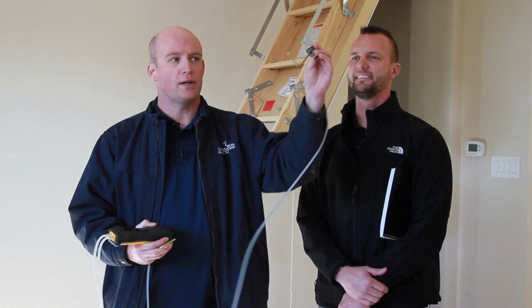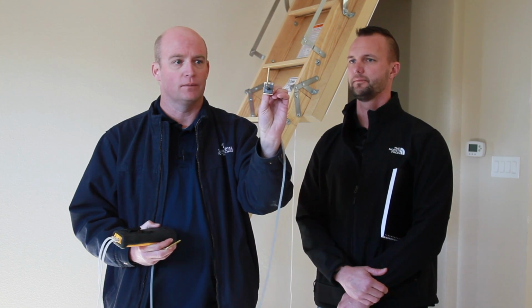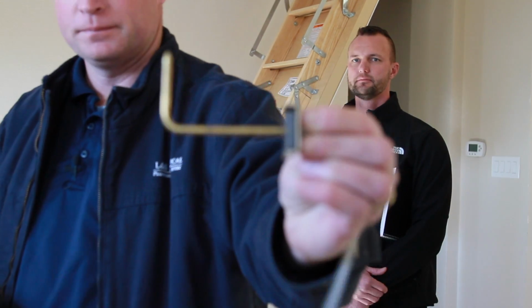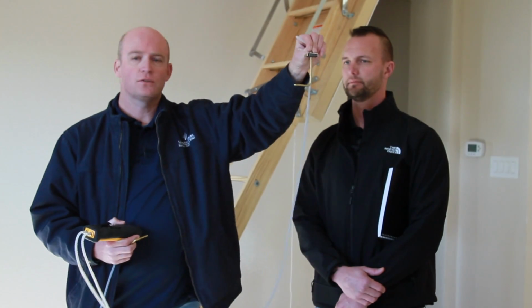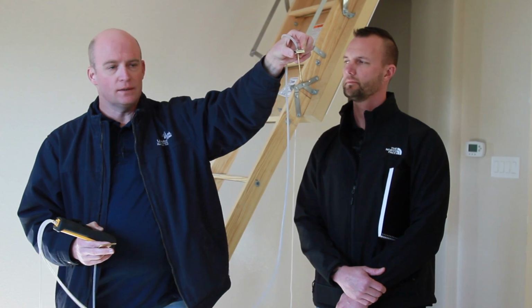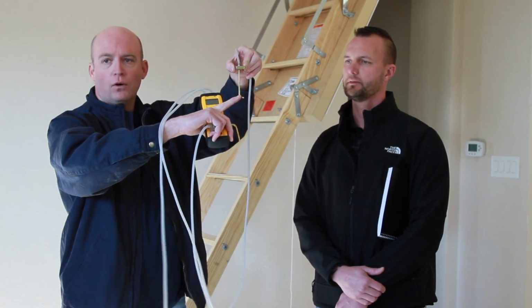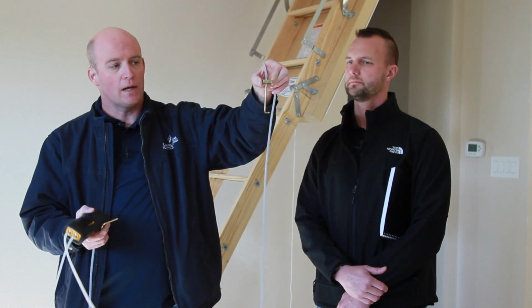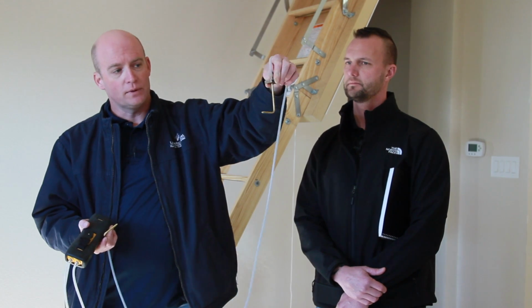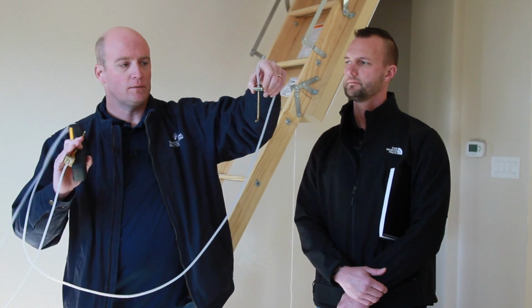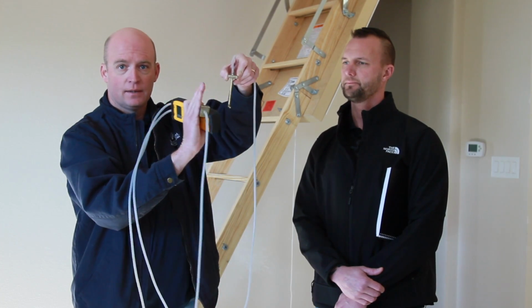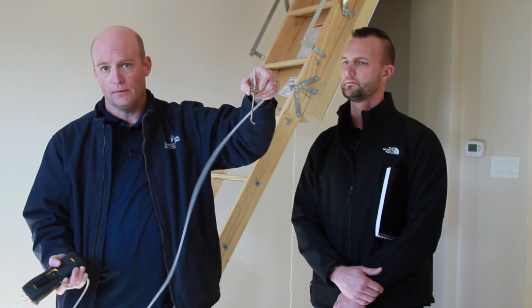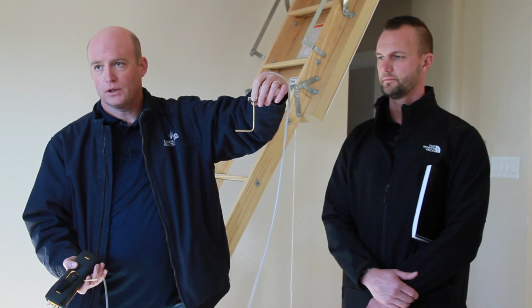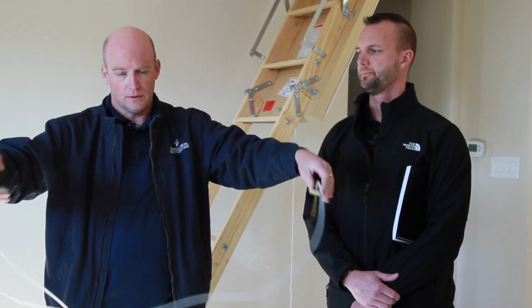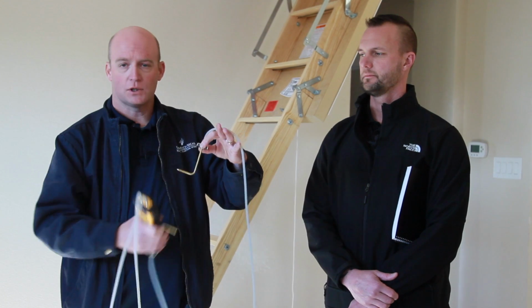If you'll notice, the probes have a point. It's not a pitot tube, but it's similar. And on the sides, there are holes. We want the probe to be pointing in the direction of the airflow. If it is pointing to the side and the airflow is hitting one of the holes, we will have an erroneous reading because we'll have velocity pressure, which we're not taking into account. If it's pointing this way, it's just static pressure. Velocity pressure would be added pressure off the blower hitting that, and that would give us an inflated value that's not realistic. But if we keep it pointing in there, the pressure would be a static pressure, that is, it's coming from all 360 degrees, and it's just a true pressure, so it makes a huge difference.